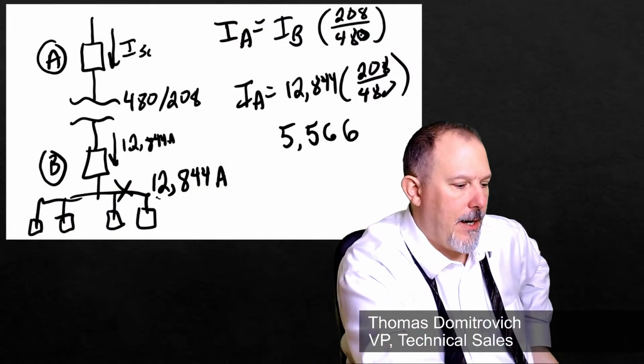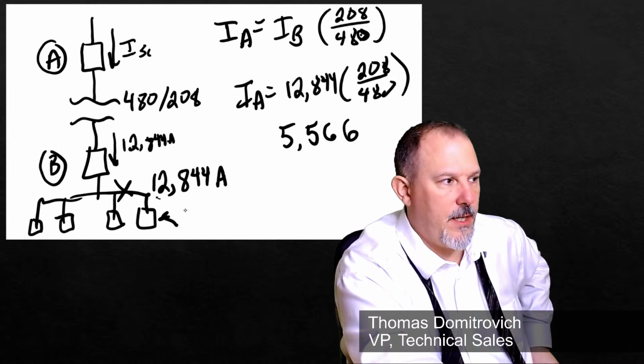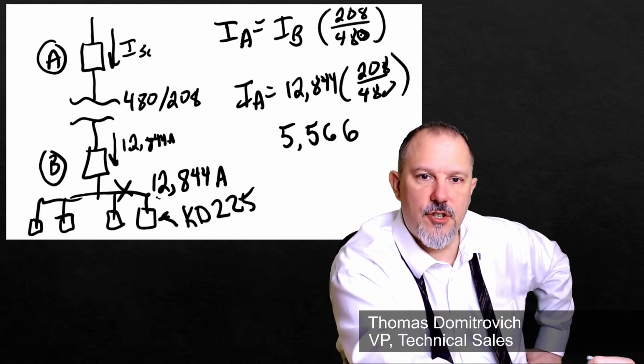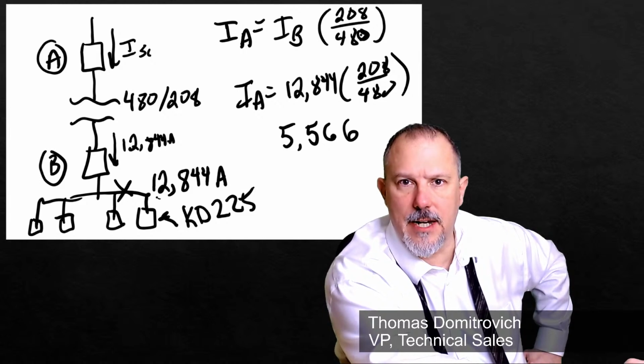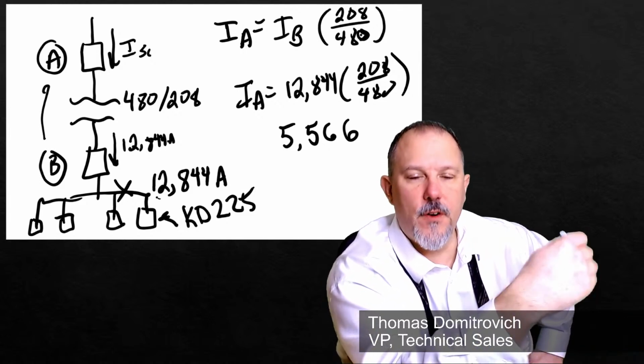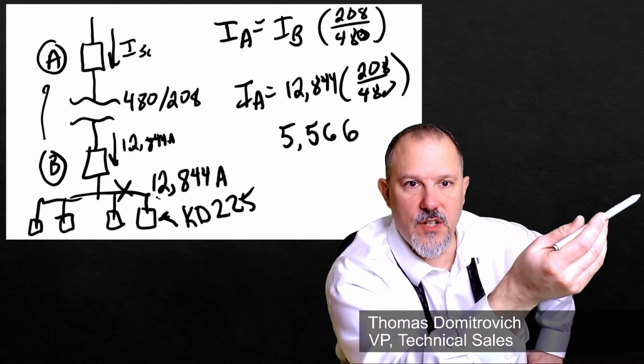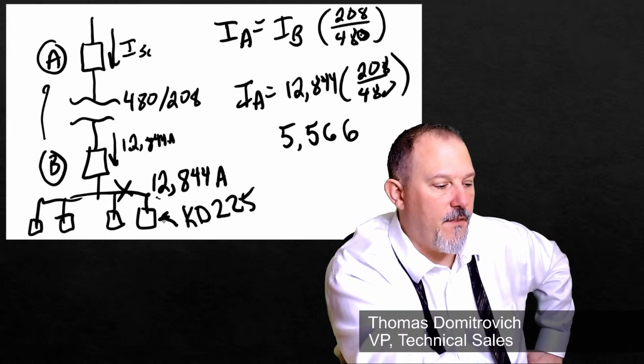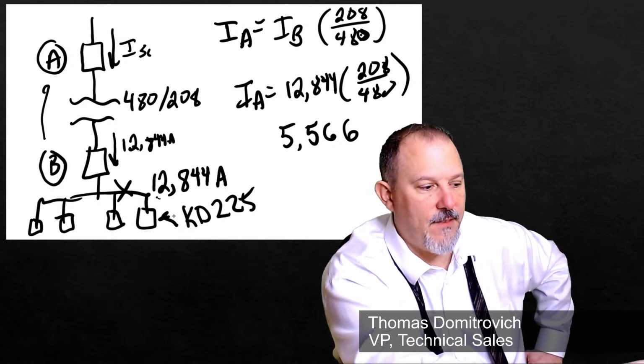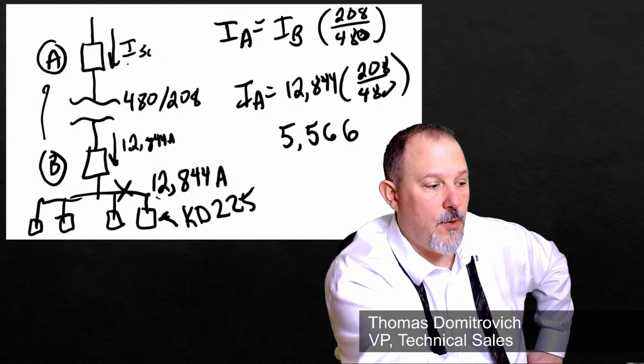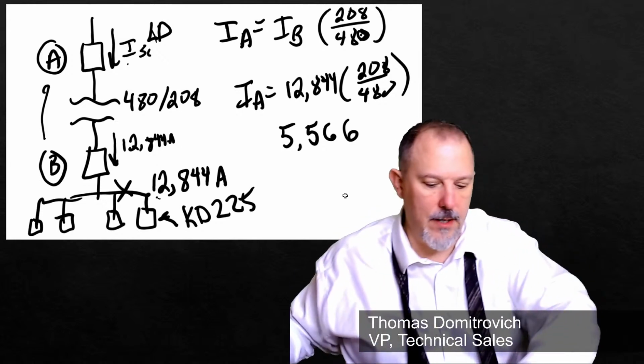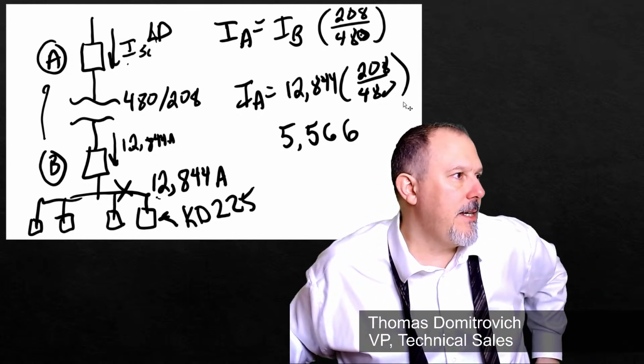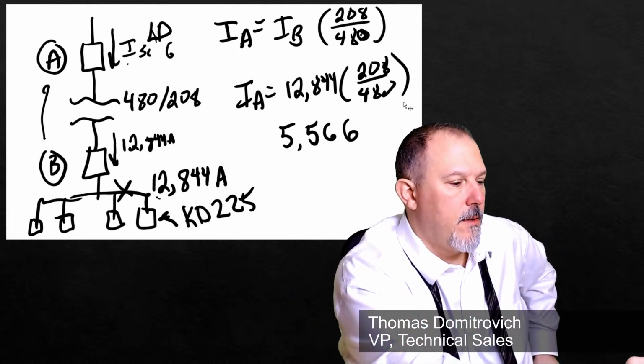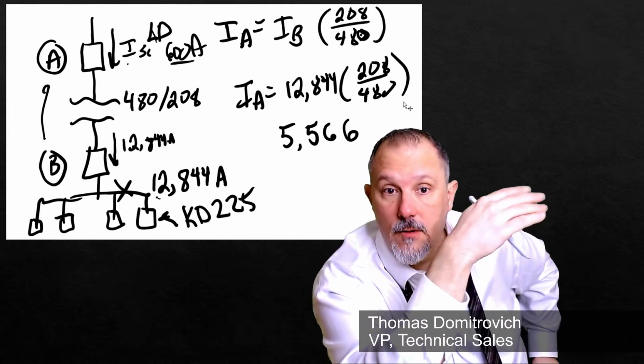So for this guy here, remember this breaker here was the KD 225. That's my branch or feeder breaker in the downstream panel. I don't have to worry about breaker B, the primary device on the secondary of the transformer, with the feeder of the transformer, because if both of them open, I lose the same load. But for a fault here, if the KD 225 does not selectively coordinate with device A, which was an LD 600 amp breaker, then I would take out more and I could lose all those others.